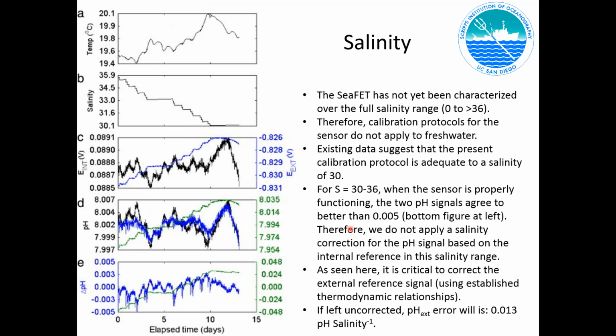Another question that we often get asked is in regard to salinity, and the answer here is probably not going to make everyone completely satisfied. The short story is we've not tested SeaFET type sensors over the full range of salinity for a variety of reasons, absence of standards mostly, but we have tested it down to a salinity of 30, which is what you're seeing in this figure, and the data here led us to conclude that in the salinity range of 36 to 30, we do not need to apply a salinity correction to the pH value based on the internal reference electrode.